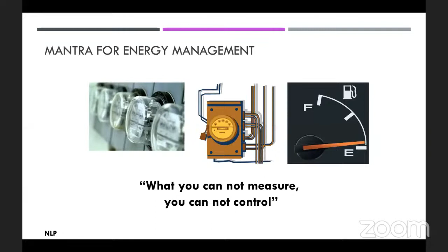Now I'll share a typical example of how loads are measured in a hospital, what percent each load is. I can't tell you the exact demand in kilowatts, but I can tell you the percentages, due to confidentiality of information. Typically, aircon is the highest load, even in industry I think. Probably because we are a tropical country, and in a hospital setup, almost 100% of the area is air conditioned because you need to make sure patients are taken care of, and the machines used need to be in a practically cold environment.